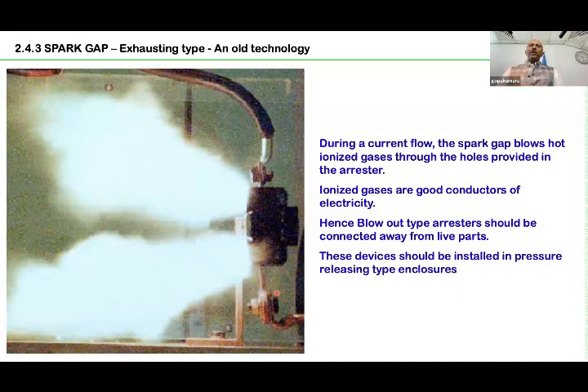Most of the time these SPDs are not available in the market from good manufacturers, but still you will get it if you go for a cheaper SPD. Cheaper in the sense, sometimes there is a tendency in India, I don't know about Sri Lanka, in India people get something from China and put a label and sell. So spark gaps have this kind of a problem. Spark over will come out. So these are called blowout type SPDs. Blowout means whatever arc is created, it blows out. So you have to mount it with special care.